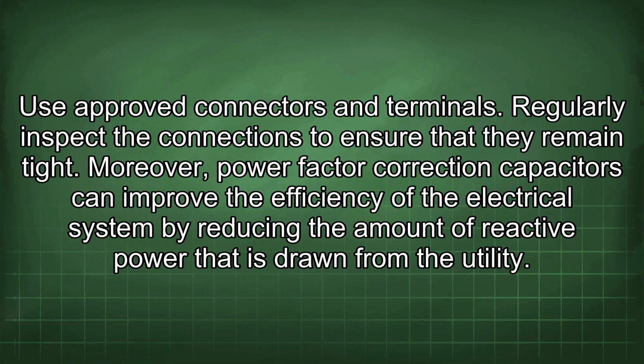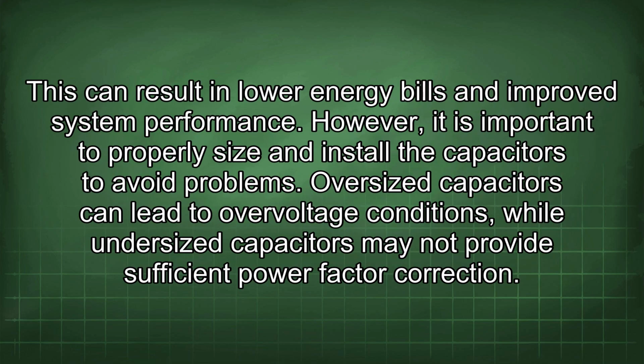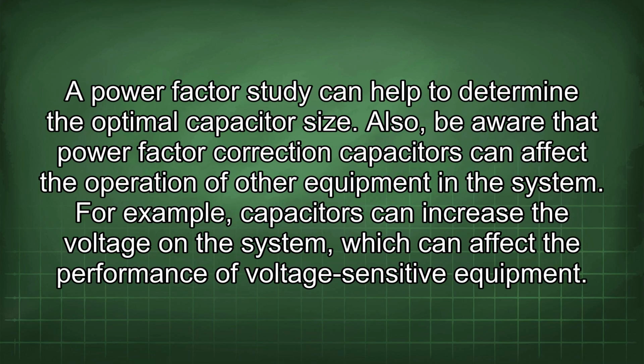Moreover, power factor correction capacitors can improve the efficiency of the electrical system by reducing the amount of reactive power that is drawn from the utility. This can result in lower energy bills and improved system performance. However, it is important to properly size and install the capacitors to avoid problems. Oversized capacitors can lead to overvoltage conditions, while undersized capacitors may not provide sufficient power factor correction. A power factor study can help to determine the optimal capacitor size.